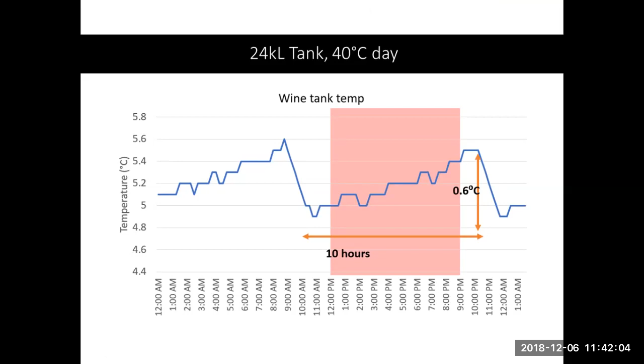The last thing I wanted to point out on this graph is what happens if we extend the cooling band to say anywhere between 4 degrees and 6 degrees. If we allow the wine to fluctuate between those temperatures, we wouldn't need to conduct any active cooling for maybe 1 to 2 days even. It would happily sit without any kind of cooling for a very long period of time. I guess that's one of the main things we can use to our advantage when we're trying to manage electricity demand in wineries.